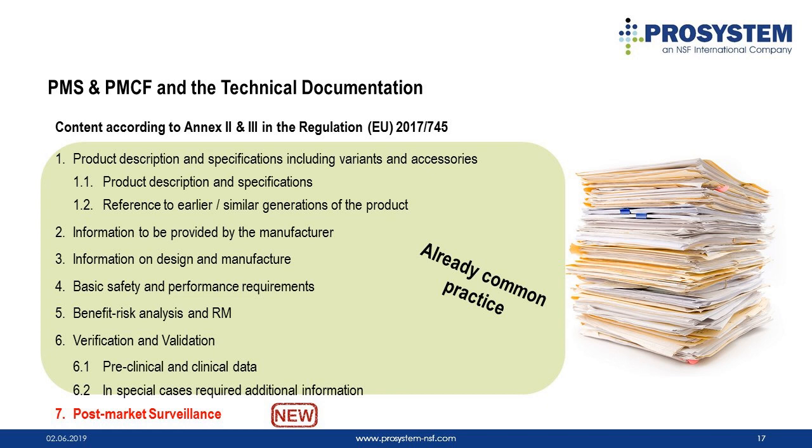Regarding the impact on the interfaces to PMS as elaborated in Article 83, it is only consistent to include the PMS documentation in the technical documentation. For example, the benefit risk analysis and risk management document will be affected by PMS findings, and after placing your device on the market, your clinical data will be extended by the PMS report.